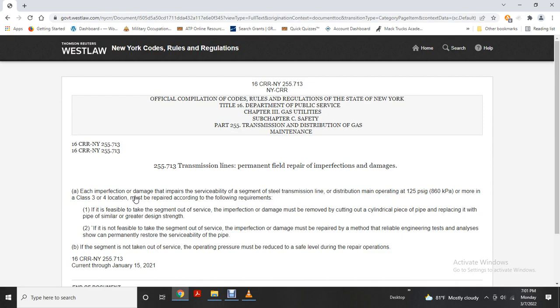Transmission line permanent field repair of imperfections and damages. Each imperfection or damage that impairs the serviceability of a segment of steel transmission line or distribution main operating at 125 psi or more in a class 3 or 4 location must be repaired in accordance with the following requirements. If feasible, the imperfection or damage must be removed by cutting out a cylindrical piece of the pipe and replacing it with pipe of similar or greater design strength.